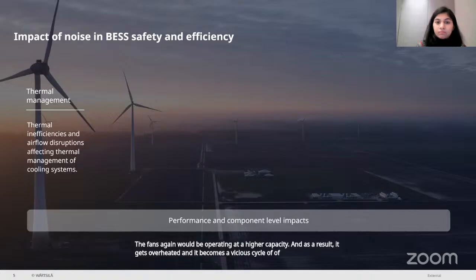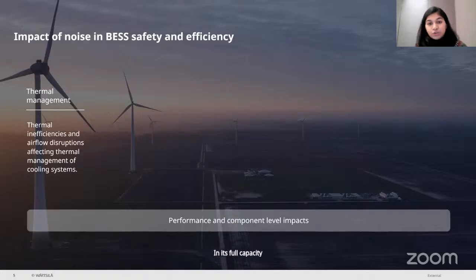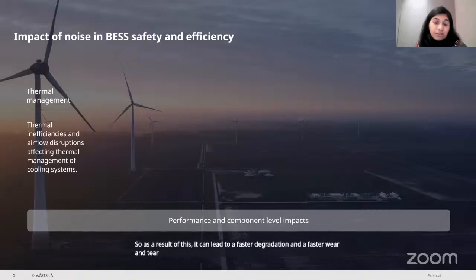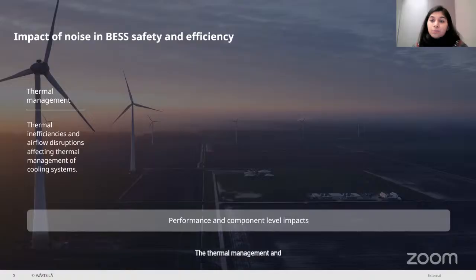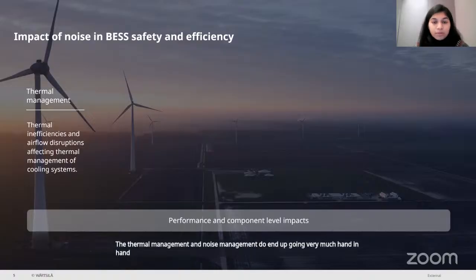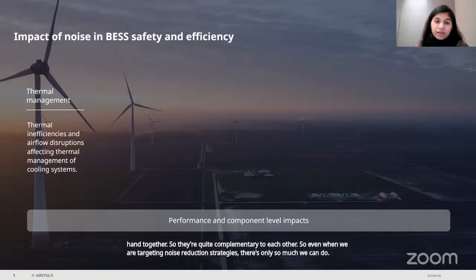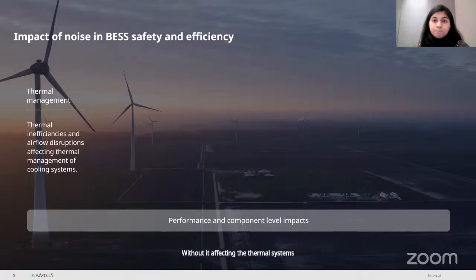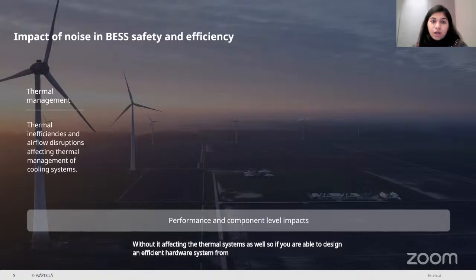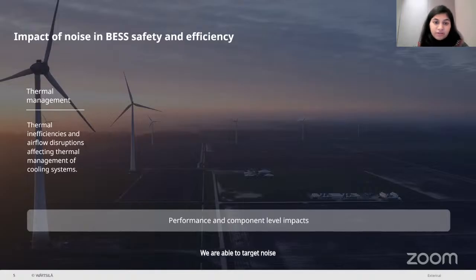of it operating at full capacity, and then having to compensate with maximum power. As a result, it can lead to faster degradation and faster wear and tear on the HVAC systems and the units themselves, which are key components when we're talking about BESS systems. A lot of the time, thermal management and noise management go very much hand in hand. They're quite complementary to each other. So even when we are targeting noise reduction strategies, there's only so much we can do without affecting the thermal systems as well. If you're able to design an efficient hardware system from a cooling perspective, we are able to target noise in the early stages of development itself.